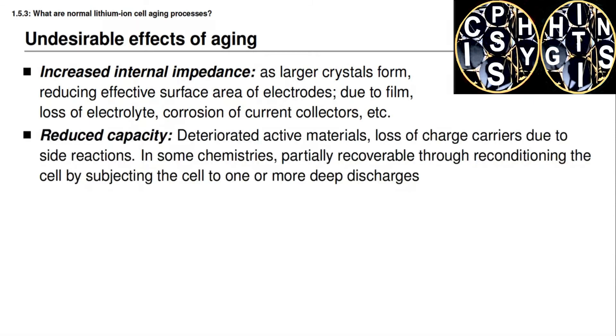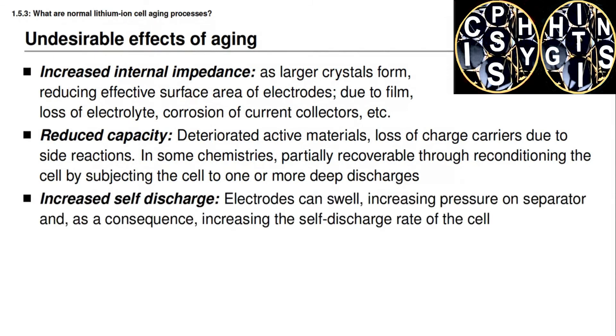A second undesirable effect is reduced capacity. When the active materials disintegrate or deteriorate, they lose vacancies that could have held lithium, or we lose charge carriers from the electrolyte when side reactions occur. In some battery chemistries this is partially recoverable through reconditioning using deep discharges, but this is not the case in most lithium-ion chemistries. A third effect is an increased rate of self-discharge. As electrodes swell, that increases pressure on the separator, decreasing its resistance and leading to increased self-discharge rates.